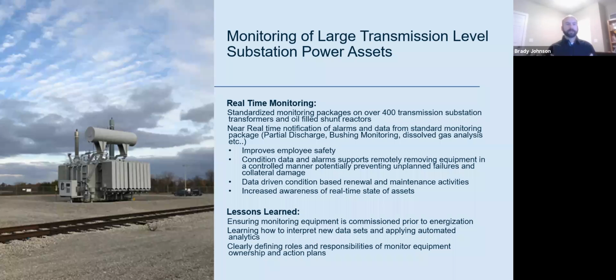When we talk about ensuring the monitoring is commissioned, that means making sure the equipment is commissioned prior to energization. We learned a hard lesson — you know the bathtub curve for transformers and reactors, right? In that very early state there's potential for them to fail, then as they get a little older they become much more reliable, and as they get older still, they're prone to fail again. From our lessons learned, we've seen units that actually catastrophically failed.